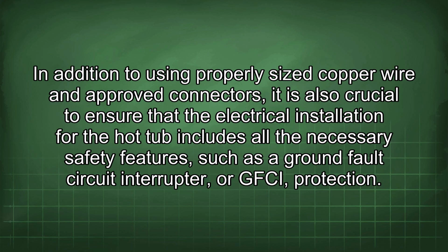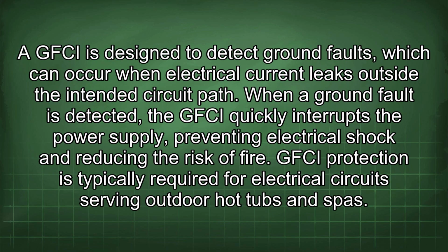In addition to using properly sized copper wire and approved connectors, it is also crucial to ensure that the electrical installation for the hot tub includes all the necessary safety features, such as a ground fault circuit interrupter, or GFCI, protection. A GFCI is designed to detect ground faults, which can occur when electrical current leaks outside the intended circuit path. When a ground fault is detected, the GFCI quickly interrupts the power supply, preventing electrical shock and reducing the risk of fire. GFCI protection is typically required for electrical circuits serving outdoor hot tubs and spas.